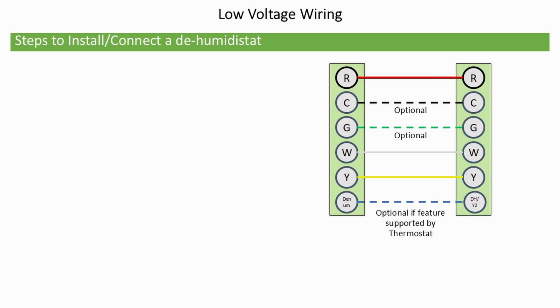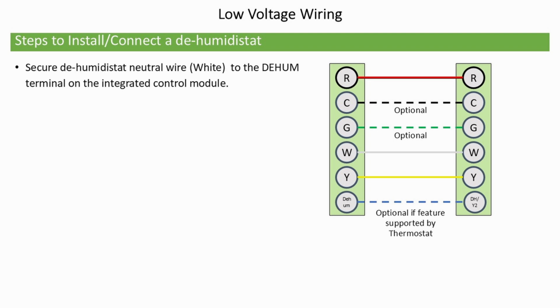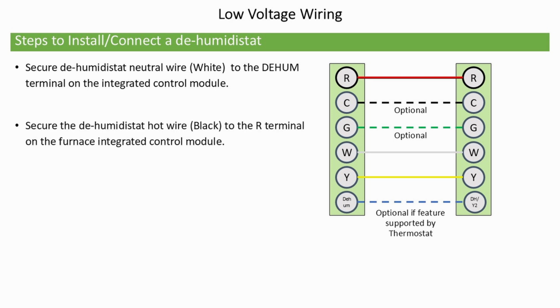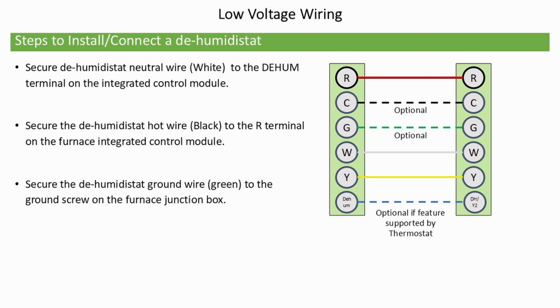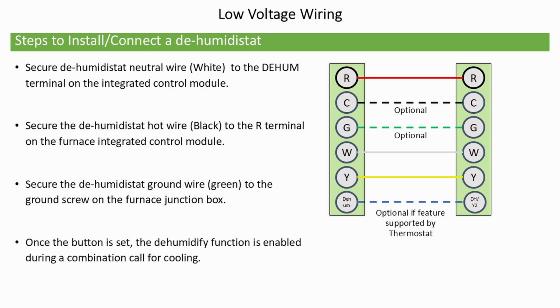Steps to install and connect a dehumidistat. Connect the dehumidistat neutral wire, white, to the DEHUM terminal on the integrated control module. Connect the dehumidistat hot wire, black, to the R terminal on the furnace integrated control module. Connect the dehumidistat ground wire, green, to the ground screw on the furnace junction box. Once the button is set, the dehumidify function is enabled during a combination call for cooling.